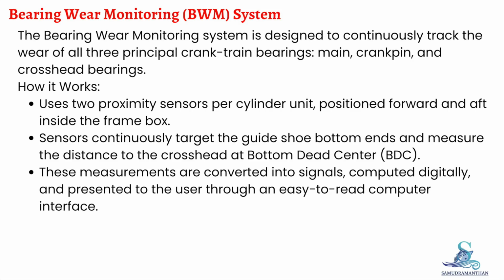Bearing Wear Monitoring System, BWM. The bearing wear monitoring system continuously tracks wear in the main, crankpin, and crosshead bearings. Here's how it works. Two proximity sensors per cylinder are installed inside the frame box, one forward and one aft. They continuously measure the distance to the crosshead at bottom dead center. These measurements are converted into digital signals and displayed through a computer interface that is easy to read.